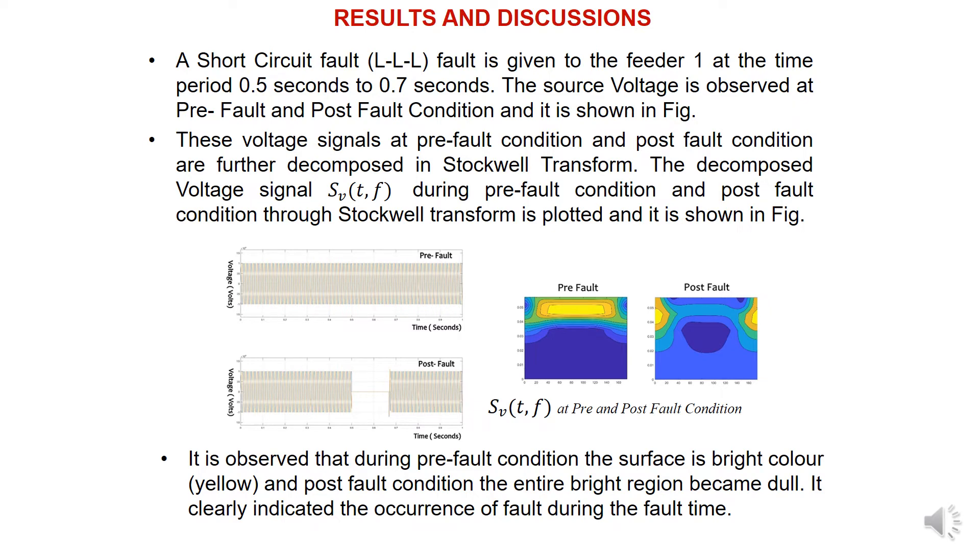You can see here on the left side the pre-fault and post-fault voltages. In the pre-fault condition, the voltage level is correct and in a good way, whereas in the post-fault condition you can see some disturbance from 0.5 to 0.7 seconds. All the voltage values from 0.5 to 0.7 suddenly got interruption. You can see some interaction between 0.5 to 0.7.